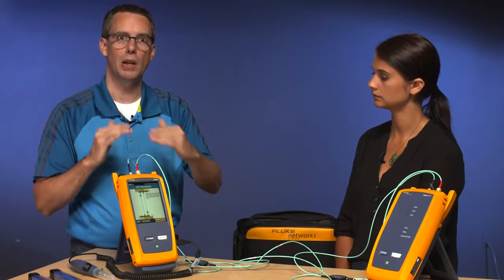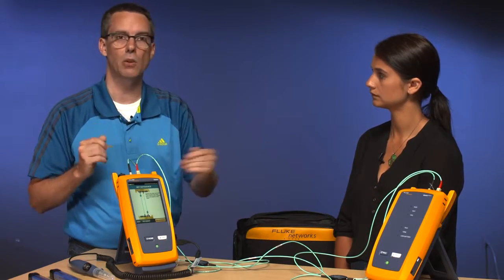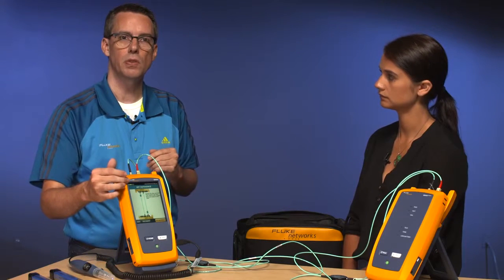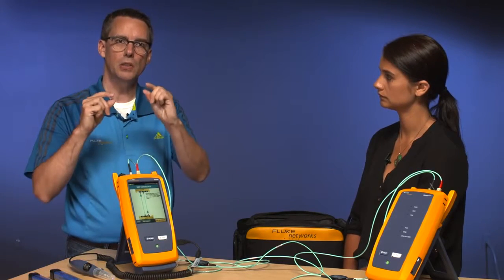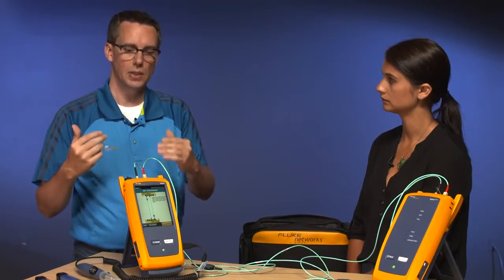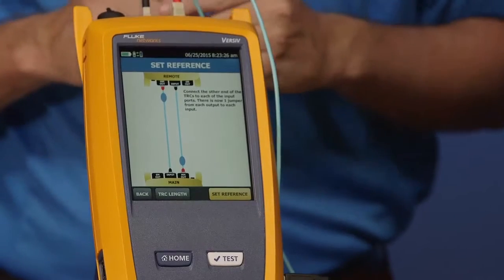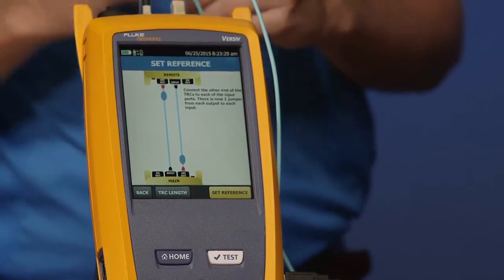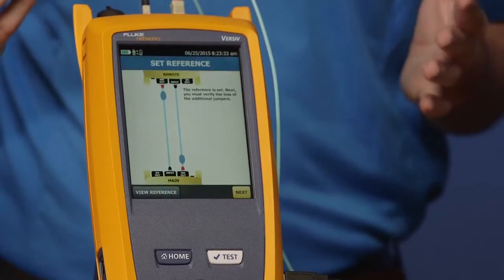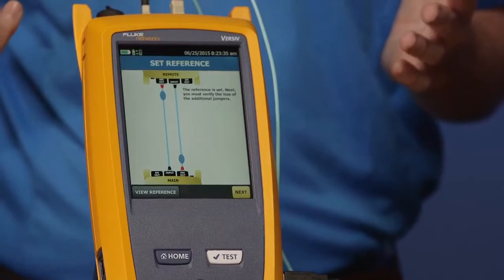You may have heard the bleep when we connected them — that confirms we got continuity and the polarity is correct between the main and remote units. In the top-left corner of the screen you'll now see two tester icons with green arrows, indicating the main is talking to the remote. Go ahead and tap 'set reference' — this takes about three seconds, much quicker than the DTX which took about 12 seconds. Our reference is set and we've zeroed out these cords.